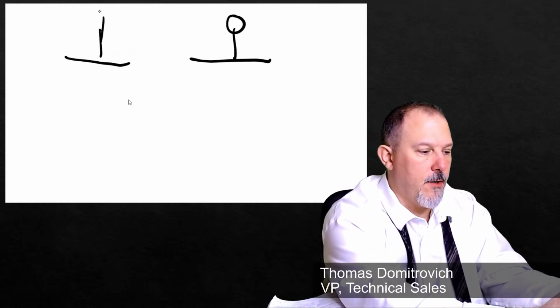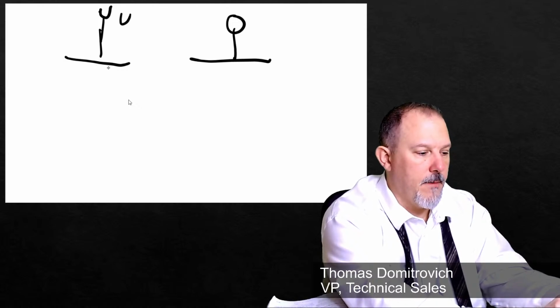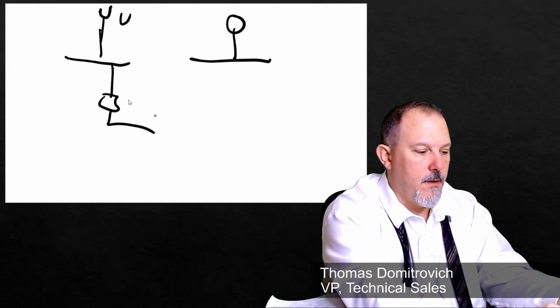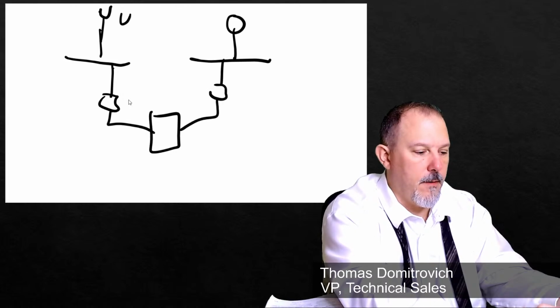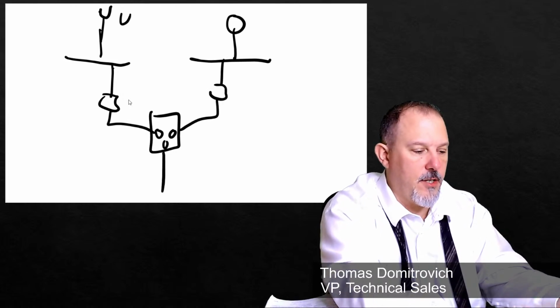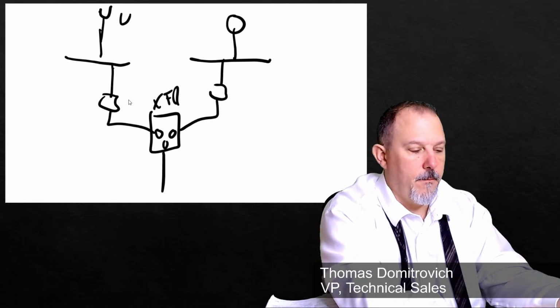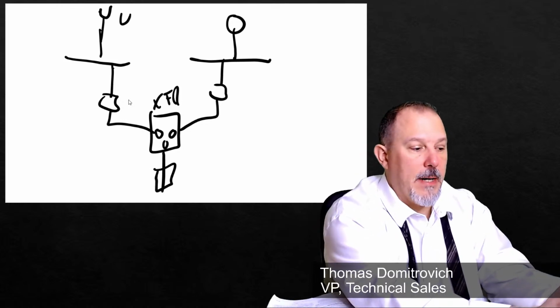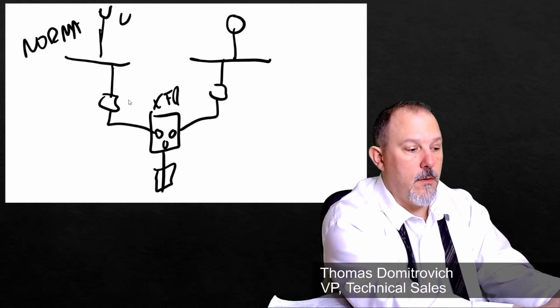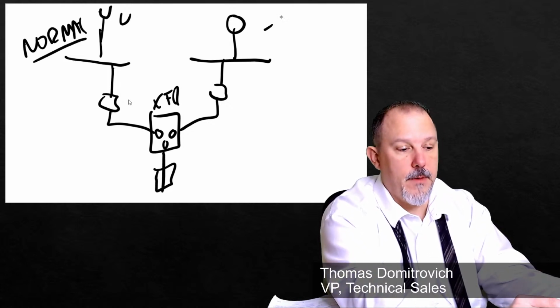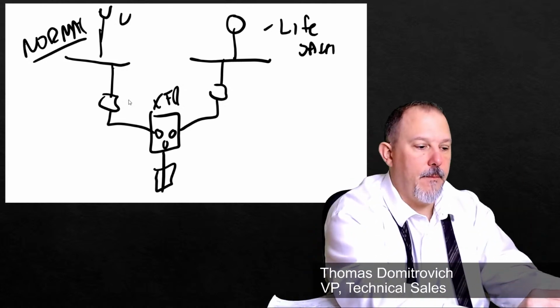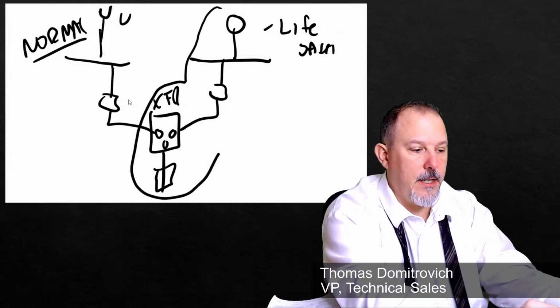Let's just draw a... I've got a utility. Got a panel here and a panel here, basically. I got a generator, and I have a utility, and I have a breaker, and I have a breaker, and then here, right? And that's my transfer switch. And I have a breaker here. So this is my normal side, right? So that's normal. And this is life safety. But technically, the life safety system is right here.